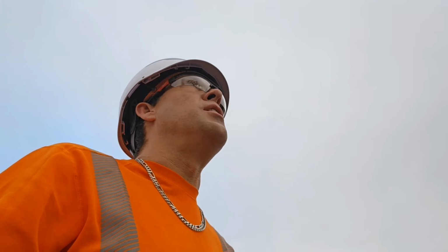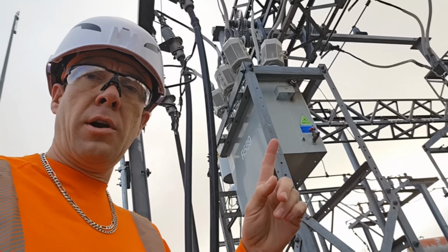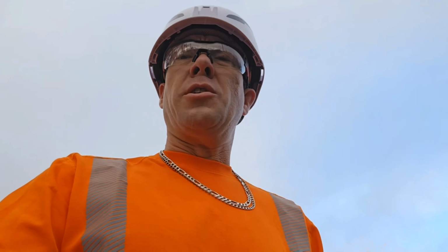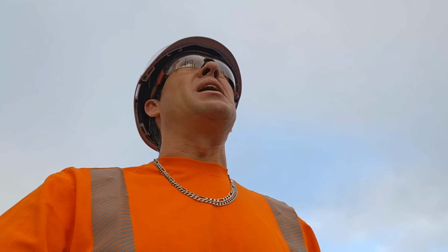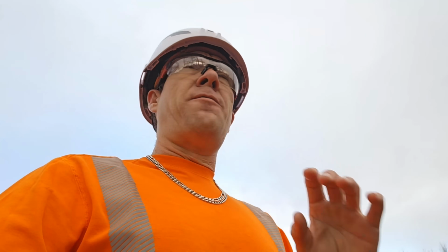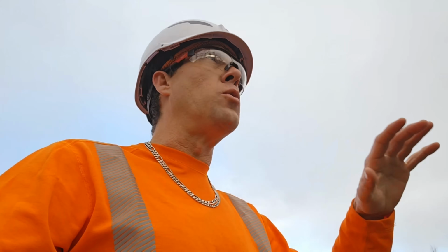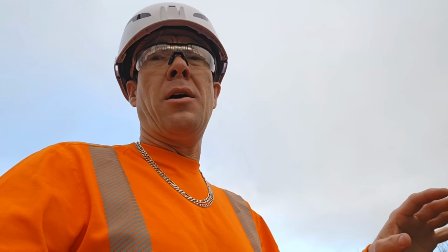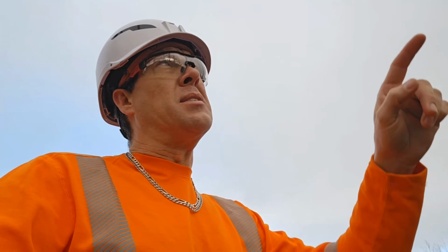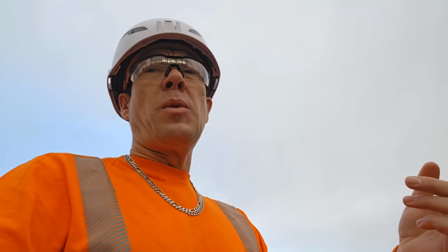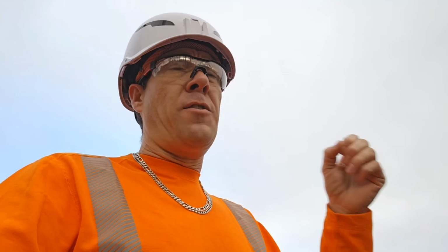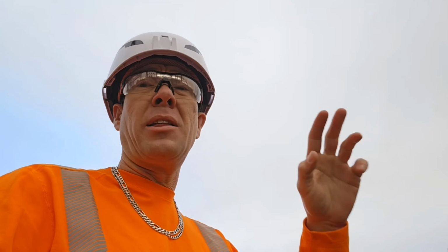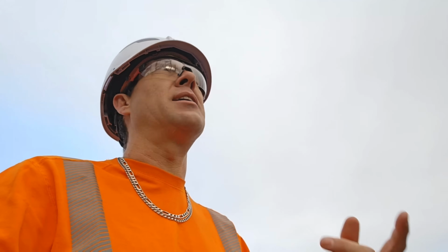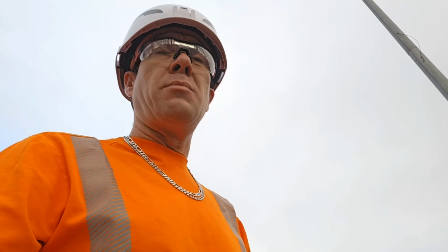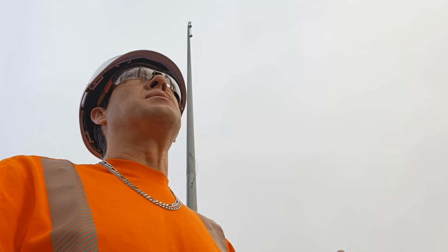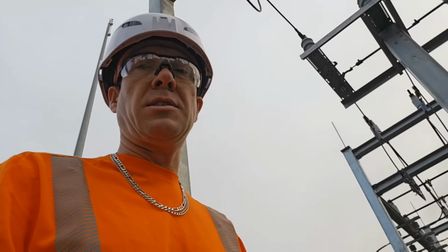In the substation now, first thing I want to show you is this unit behind me, called a recloser. During storms or incidents, could be an animal getting into the lines, a bird or something, that fault current is going to electronically shut off the whole grid. What happens is it automatically turns back on. That's why sometimes your lights go off and right back on, because those units feed probably about 500 customers. Maybe the bird got on a sideline feeding one customer, the fuse at that sideline is going to blow, that unit shuts off, and automatically turns back on, restoring power to the other 499 customers without us even having to respond. So that's why sometimes your lights go off and back on. It's a normal system process to avoid massive outages.